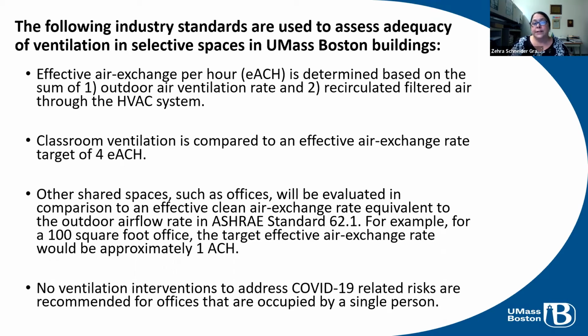In other shared spaces, like an office, they would be evaluated compared to an effective clean air exchange rate equivalent to the outdoor airflow rate in ASHRAE standard 62.1. So this is the industry standard to look at outdoor airflow rates. For example, in a 100 square foot office, the effective air change rate that we would be looking at would be 1 air change per hour. So different than a classroom space where you have a much larger space with a lot more people.